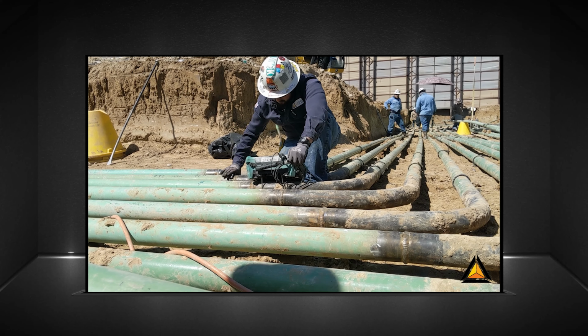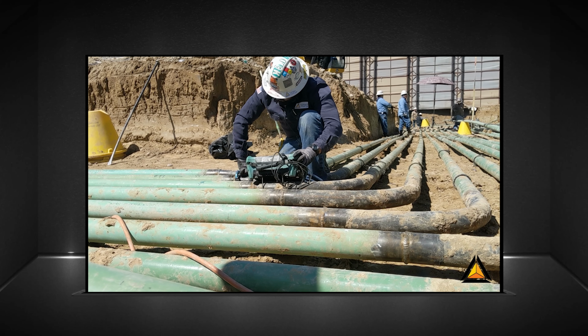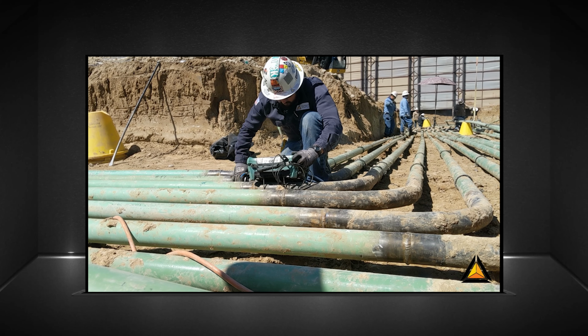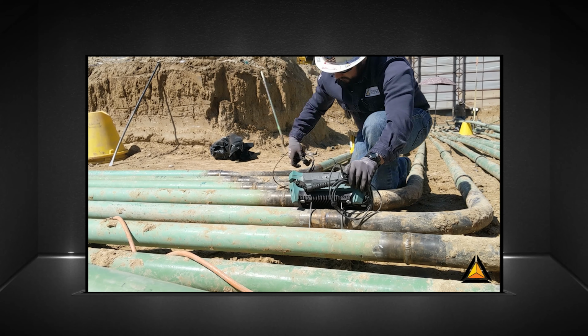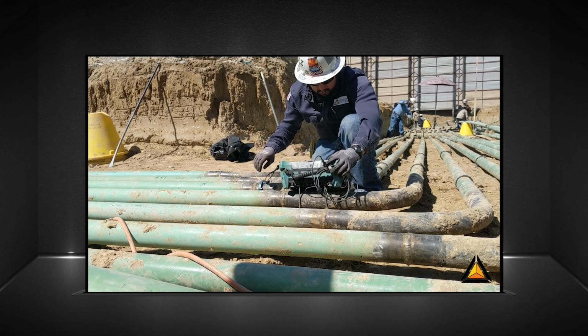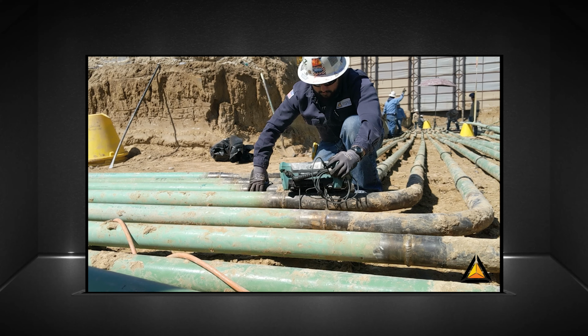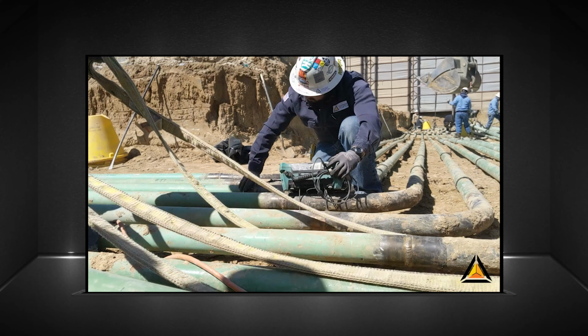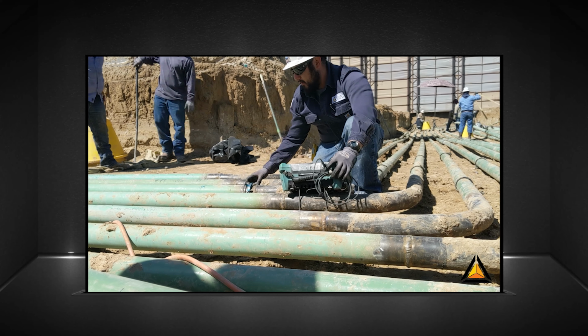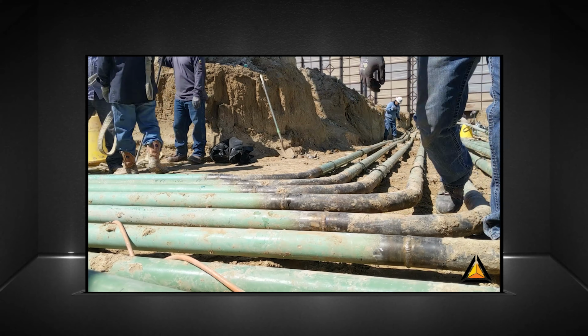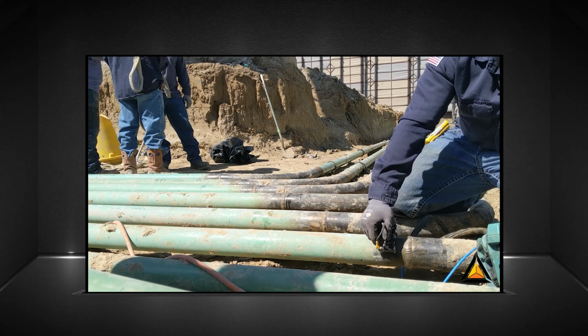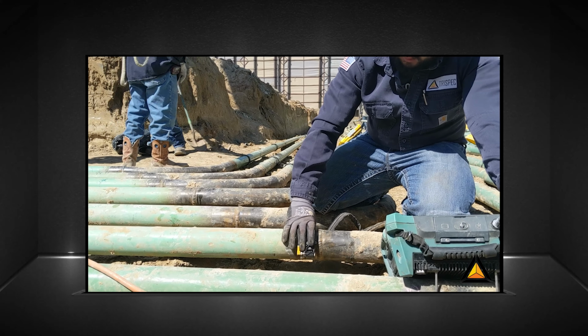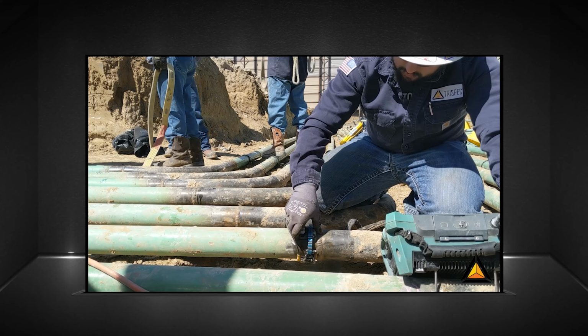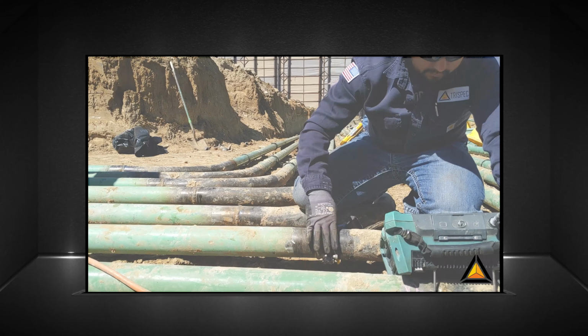Lastly, we will look at the implementation of phased array on small bore piping in higher trafficked areas. Jose Tapia is scanning multiple 3-inch Schedule 160 welds. Notice how there isn't a need to close off areas or stop all work due to radiation concerns, because phased array utilizes the safest technology available for volumetric inspections. The same technology used by doctors performing ultrasounds on babies in the womb.